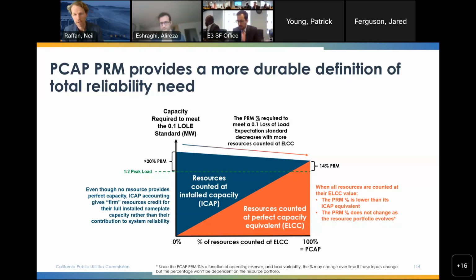The other benefit, which this chart gets at, is that we expect it will provide a more durable reliability need determination across the planning horizon, because the perfect capacity total reliability need, and therefore the equivalent perfect capacity planning reserve margin, is not dependent on the resource portfolio. It's instead driven by load shapes, load variability, and the need to hold operating reserves.